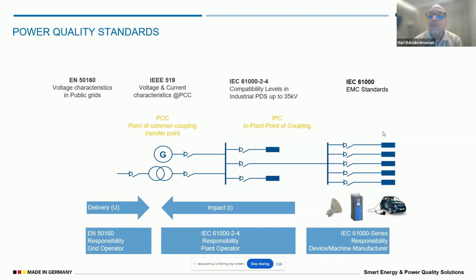Say, for example, if an equipment manufacturer says that I am IEEE 519 compliant, that is at the PCC. But how can that standard be applied to equipment which is in the consumer premises? In this case, what we can understand is, if there are no other loads in the consumer's premises and he is directly connecting it at the point of common coupling, then this complies to IEEE 519.